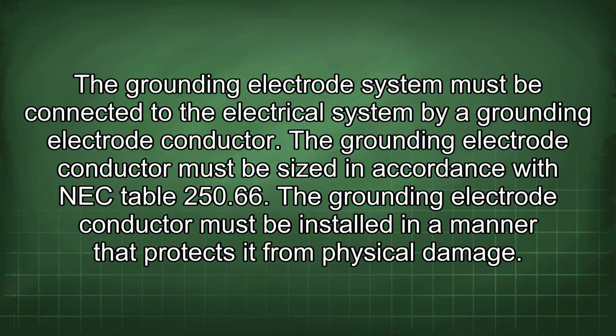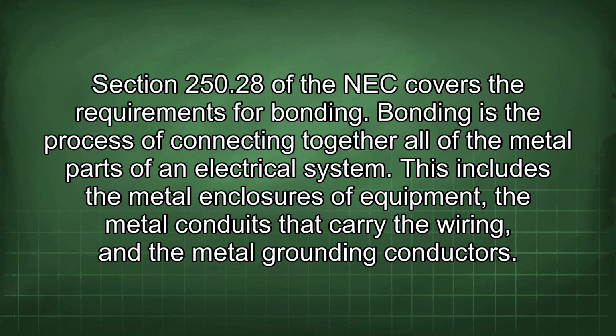The grounding electrode system must be connected to the electrical system by a grounding electrode conductor. The grounding electrode conductor must be sized in accordance with NEC Table 250.66. The grounding electrode conductor must be installed in a manner that protects it from physical damage. Section 250.28 of the NEC covers the requirements for bonding.